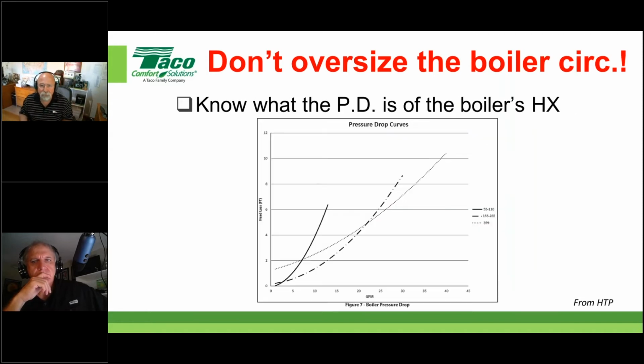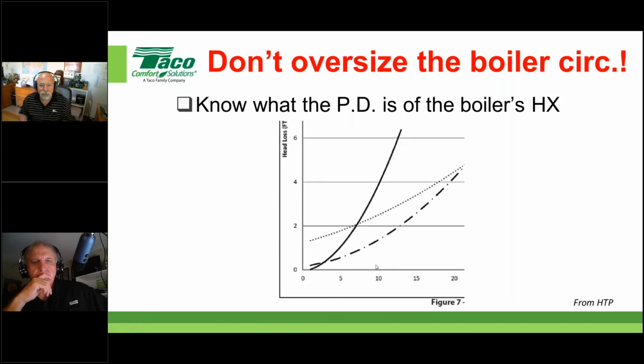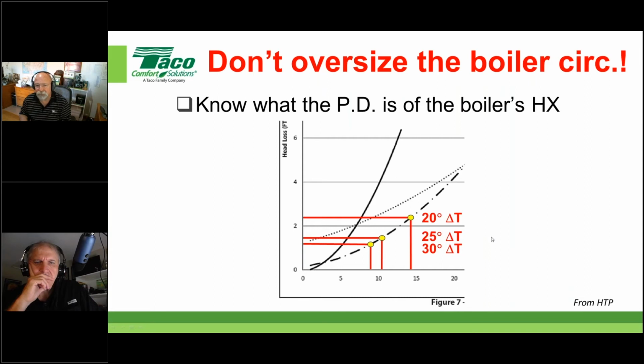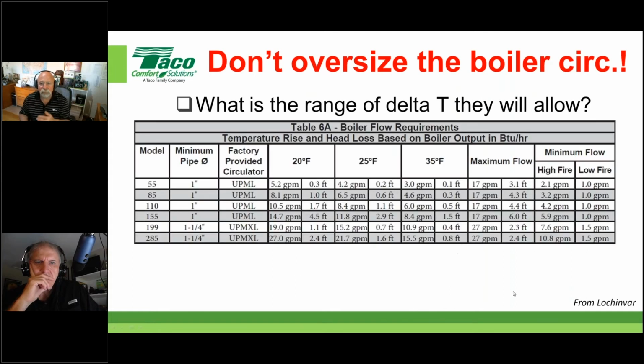Good point, John. This is just a blow up showing you how to read their curves. Again, this was done at the factory to make sure what the resultant pressure drop would be at a given flow. Now they're showing you this is the curve for the 155, and here's what it would be at a tighter delta T, and at an even tighter delta T. They're just showing you there's not a lot of head loss here in feet. So for the sake of time, let's go to the next one.